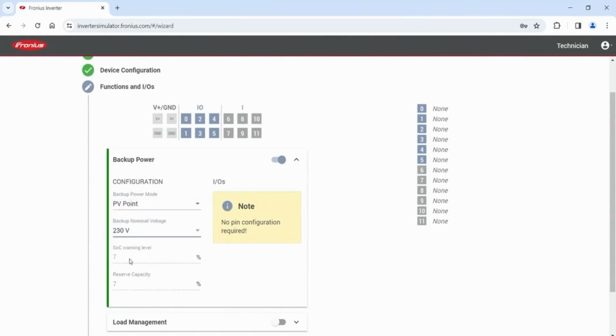Last but not least, you can determine an SOC warning level where you will get a notification before backup power mode will stop, as well as a reserved capacity. Whenever you are using stationary battery systems, you can use the reserved capacity to make sure that at least a reserved capacity is available for your backup power functionality.